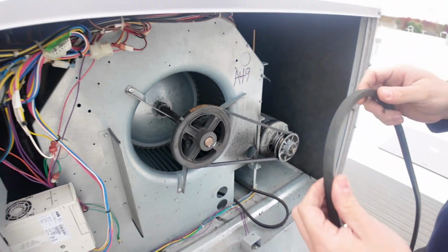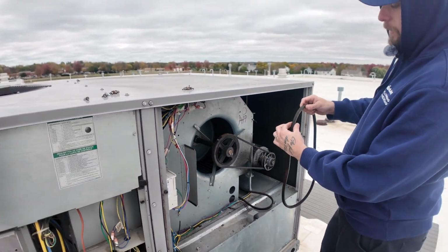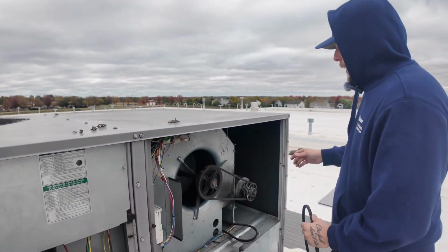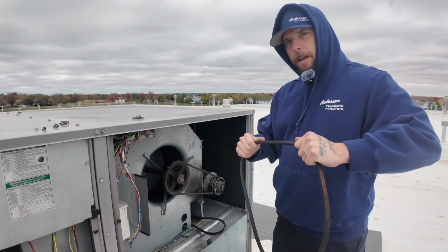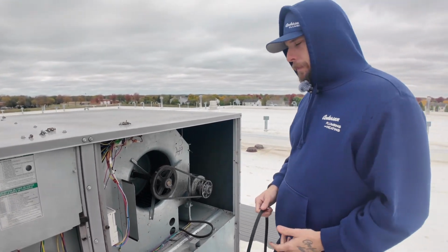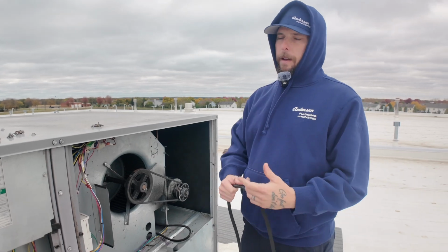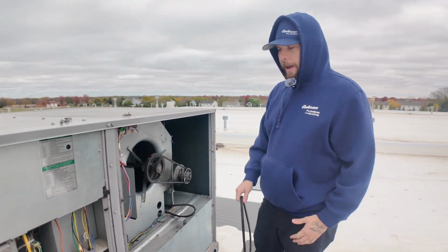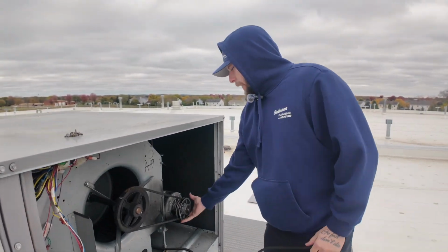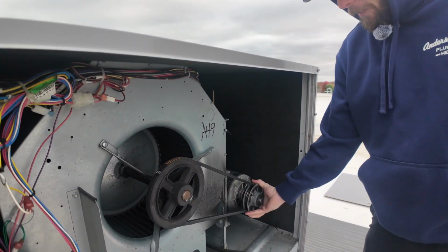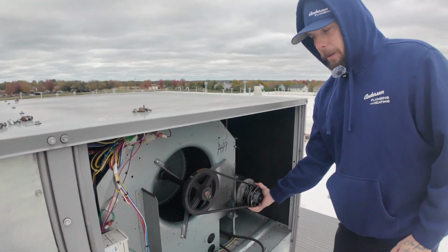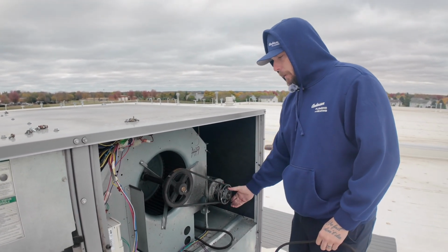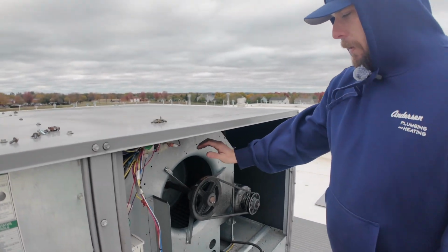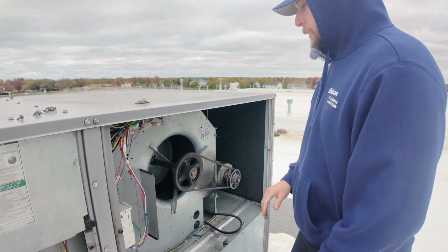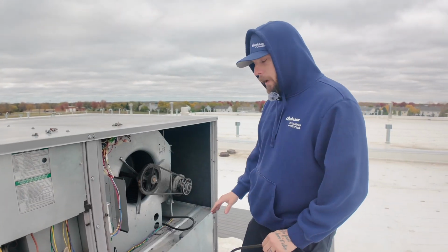Because what happens is if you don't have those two nice flat surfaces mating to each other, you're not going to get good traction on this belt, which is going to cause it to slip. And if it slips, it burns the belt up and the belt breaks, and now you've got no fan. We check the pulleys on the motors, check the bearings for end play and lateral play. Make sure that those are all good, change the belts. We put a new belt on it every single time, no matter what.